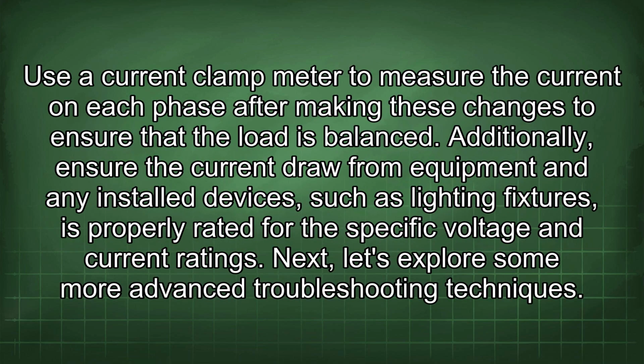Use a current clamp meter to measure the current on each phase after making these changes to ensure that the load is balanced. Additionally, ensure the current draw from equipment and any installed devices, such as lighting fixtures, is properly rated for the specific voltage and current ratings.